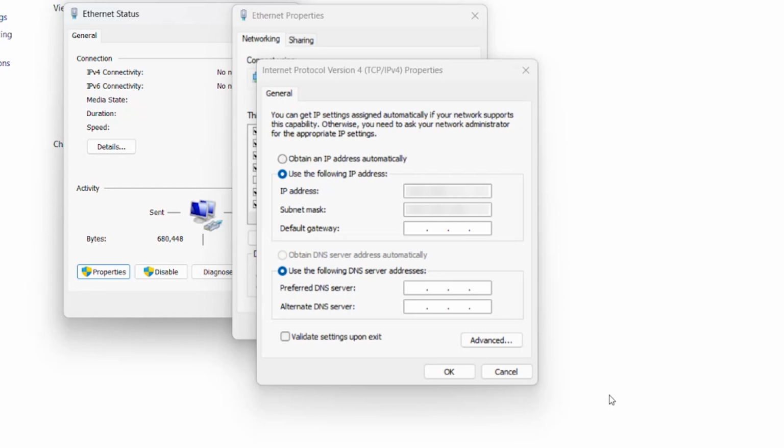So what we are going to need to do is change that IP address. What we're going to use as a starting point is the IP address that you can see on the display on the Axos system. And we're going to need to make a minor modification. With that last digit of the IP address, this number needs to be 2 higher or 2 below that number in order for there to be communication.